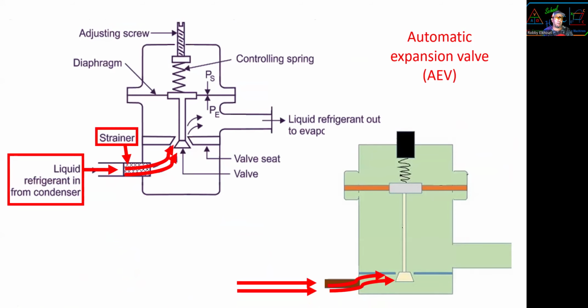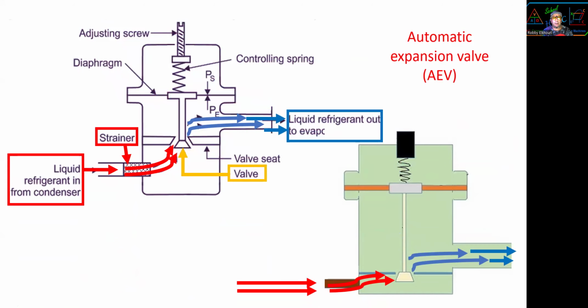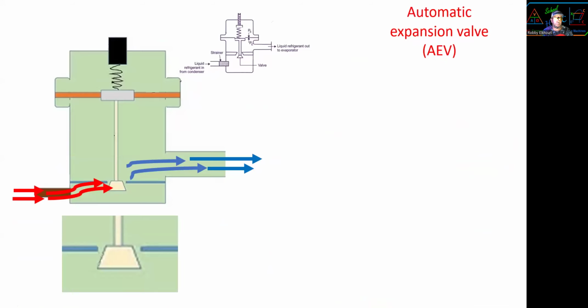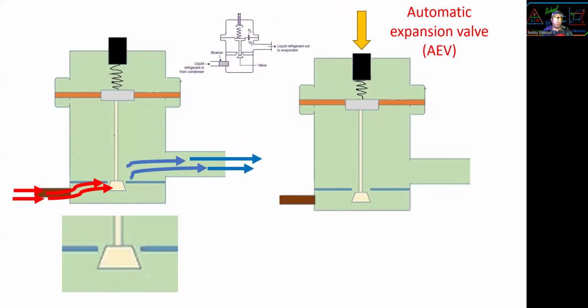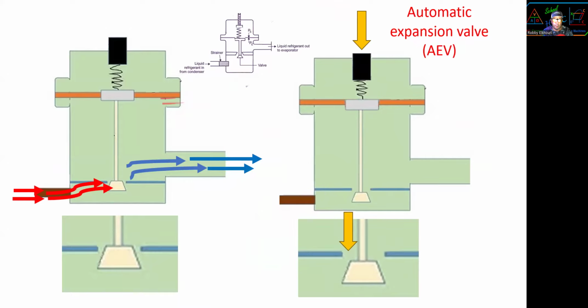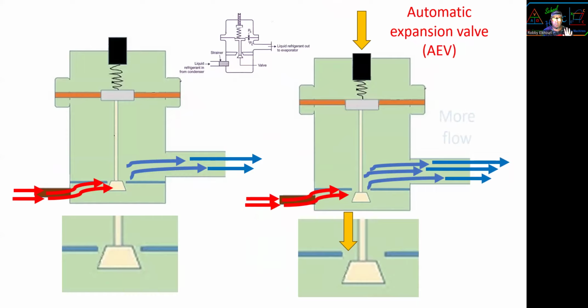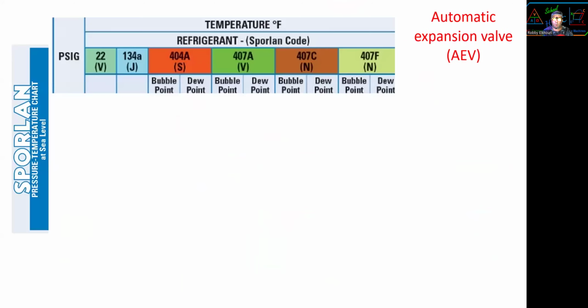All right, automatic expansion valve. We have the strainer. Liquid goes in, we have a strainer. We have the valve and the seat, and liquid refrigerant goes out, liquid vapor mix. And the control spring on top. Okay, so now, if we adjust it down, it's going to open and let more refrigerant in. So we can adjust it manually and leave it. More flow, the higher saturation temperature, pressure, higher boiling point.